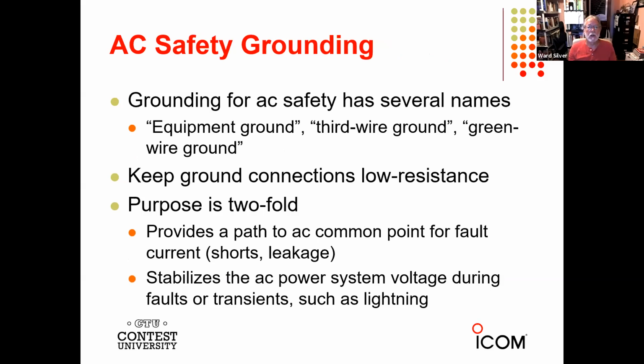Okay, safety grounding. Depending on where you live in the country and how old your electrician is, the grounding conductor can have several names. The equipment ground is the current term in the NEC. It's also called third wire ground or green wire ground. That is the connection back to the AC service box. You've got to keep ground connections low resistance. The wavelength is really long, frequency is really low, so inductance really doesn't count that much.